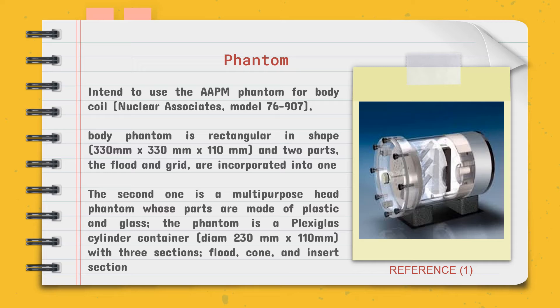The second is a multi-purpose head phantom made with plastic and glass. The phantom is a plexiglass cylinder with a diameter of 230 mm and 110 mm in length. It has three sections: the flood, the cone, and the insert section.